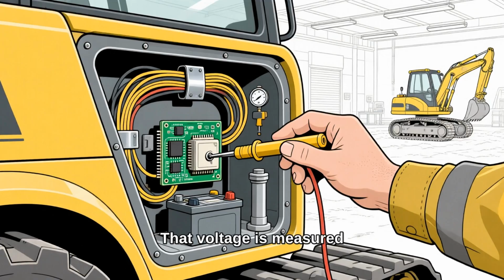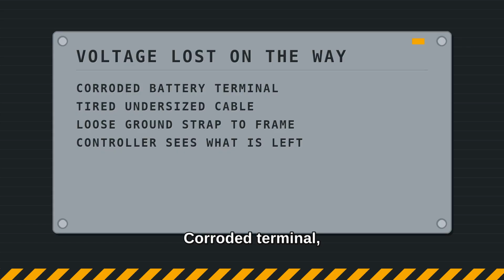That voltage is measured at the controller, not at the post. Everything in between gets to skim off it. Corroded terminal, tired cable, loose ground strap. The controller reports what reaches it, and less is reaching it.